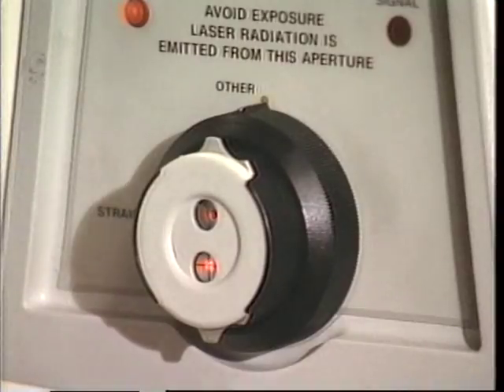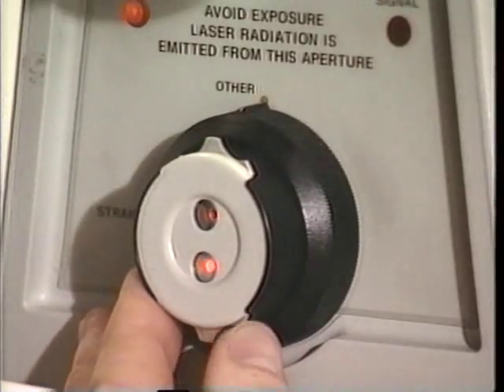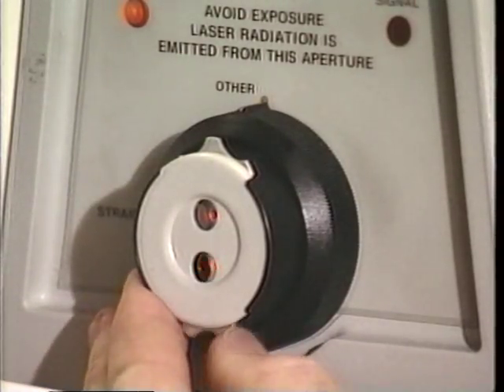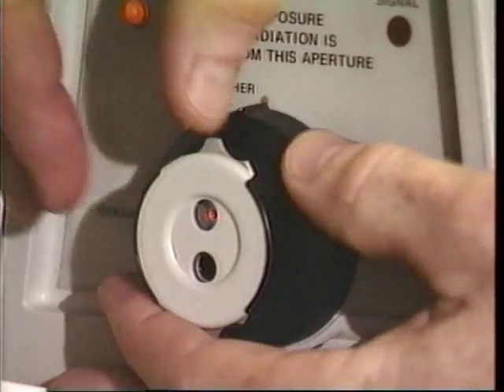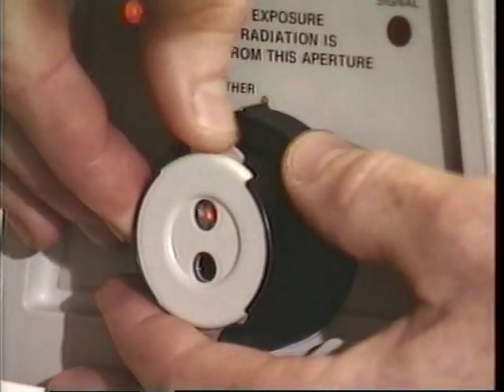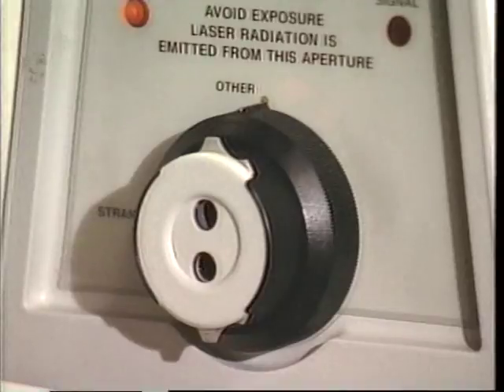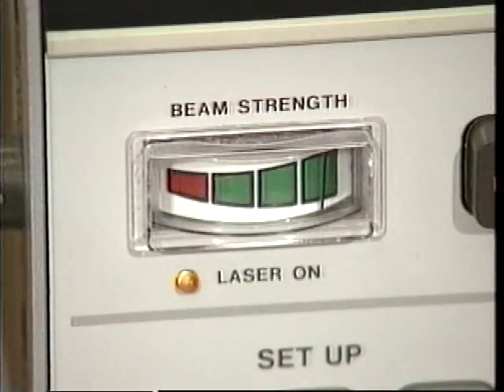Continue this process until the far end of travel, that is, the maximum separation of the interferometer and the retroreflector, has been reached. Upon completion of this procedure, the optics will be aligned. Rotate the target away from the return port and adjust the beam aperture control so that the large opening is selected. If the system has been properly aligned, the needle on the beam strength indicator should remain in the green zone over the entire range of travel.